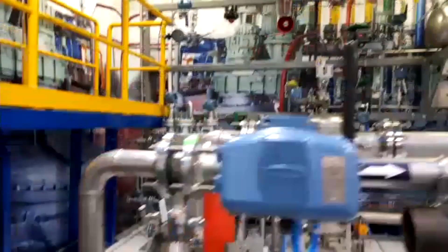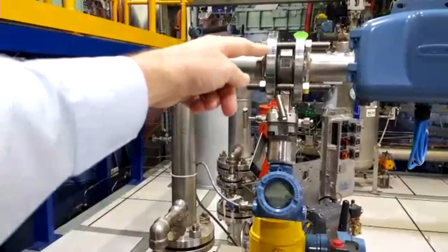So the other thing I spoke about was DP flow sensors. Here's a DP flow meter using a compact orifice plate, only 25 millimeters or 1 inch. We managed to insert it simply by prying the flanges apart and slipping in the flow meter. So not entirely non-intrusive, but still very easy to install, without cutting, drilling, or welding.